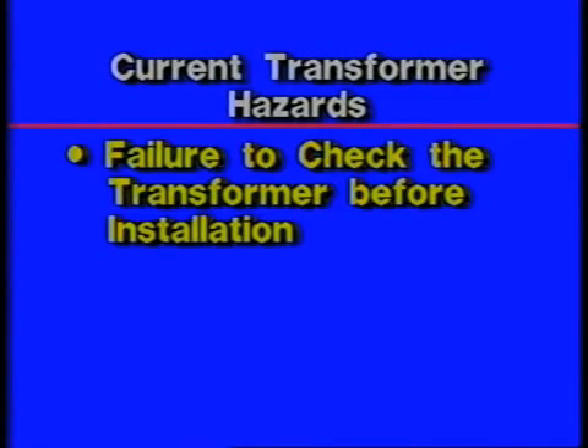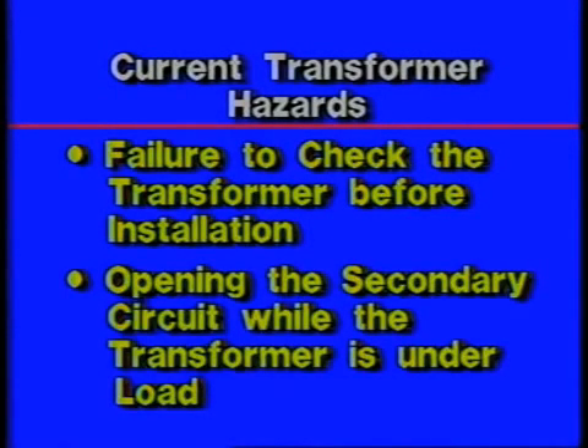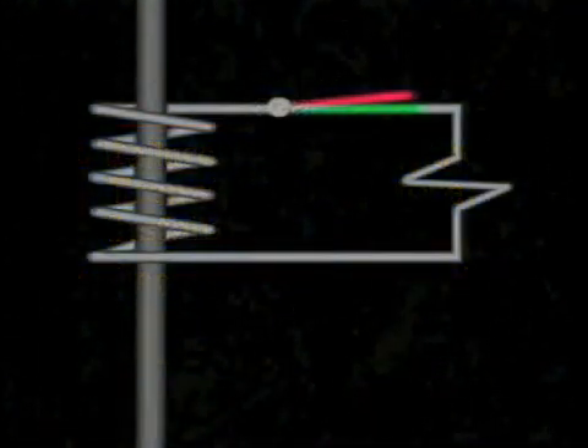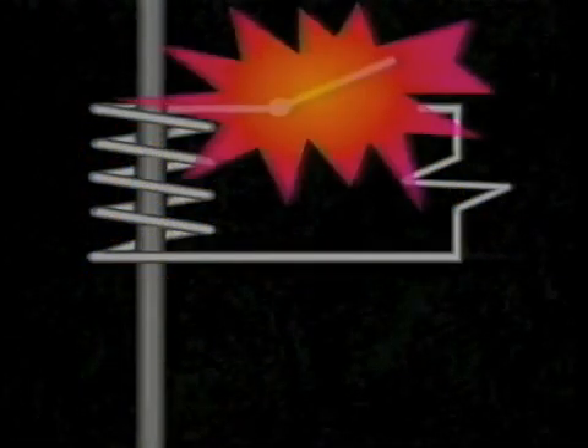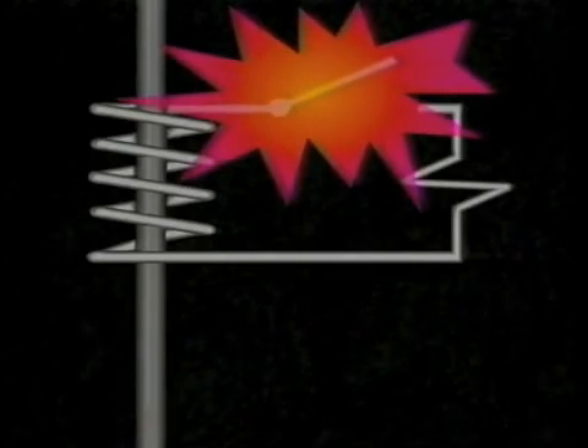Hazardous situations associated with work on current transformers include failure to check the transformer before installation. The correct type and rating transformer must be used, and the secondary circuit must be complete before the transformer is energized. Opening the secondary circuit while the transformer is under load. This causes a very high voltage on the secondary side that can produce severe shock, arcing, and blast hazards. Under no circumstances should the secondary circuit of a current transformer be opened while the primary is carrying current.